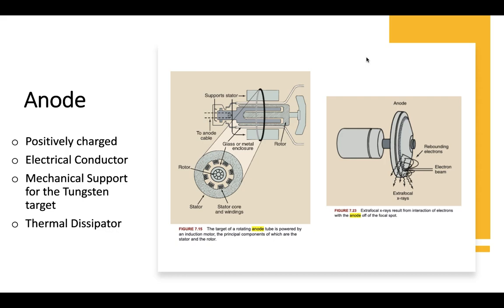The advantages of the line focus principle are the improvement of spatial resolution and heat capacity. The disadvantage is that radiation intensity is greater on the cathode side than the anode side, which is classified as the heel of the anode effect. Heel effect. Anode heel effect.